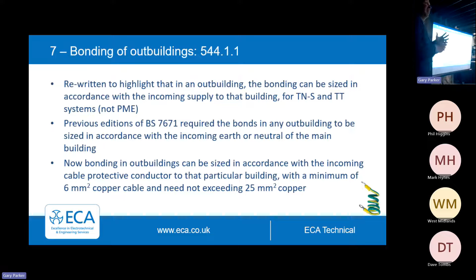Does that mean I need a 50mm cable to that smoker's hut and to that security gate? It used to say that. Now it's been clarified where you've got a TNS or TT, you can bond it with relation to the size of the incoming cable. So it just means you can design it a bit better, a bit differently, taking common sense into consideration, and end up with a much smaller cable or bond going into that far outreaching building. So it might not affect you, but it might mean you save a massive amount of copper, because we haven't got all of the copper. We have a limited, finite amount. Let's use it where we need it.